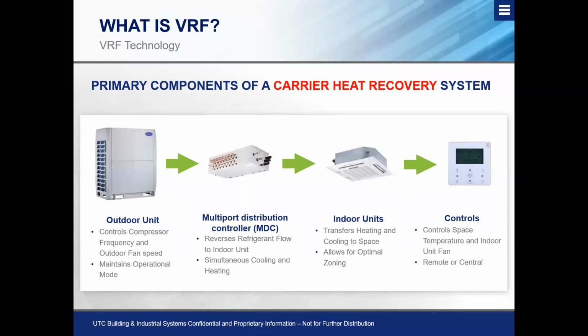Okay, but essentially what this box does is it reverses the refrigerant flow to the indoor unit depending on which one of those units are calling. And again, as I stated before, this allows that simultaneous heating and cooling, using a byproduct of one zone where we would traditionally vent out to the outside. And we're now going to use that byproduct to provide heating and cooling as needed, to be energy efficient and also meet the needs of the user.